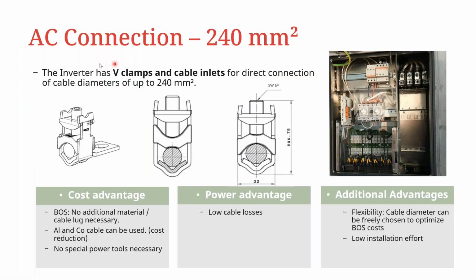So in terms of the cable glands or the V clamps that are integrated for AC connection, this can be used to connect to a maximum of 240 millimeter square. I think we've already mentioned that. And it has a very unique design because you can actually flip it over, as you can see in these 2 illustrations. So in the second illustration, that holds a smaller cross-section of cable.